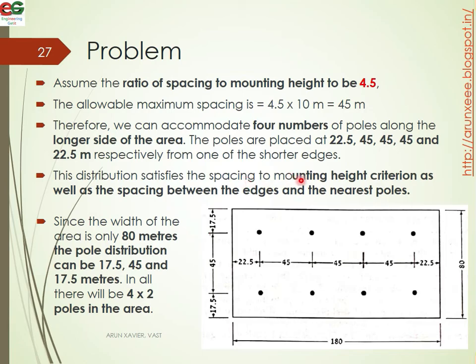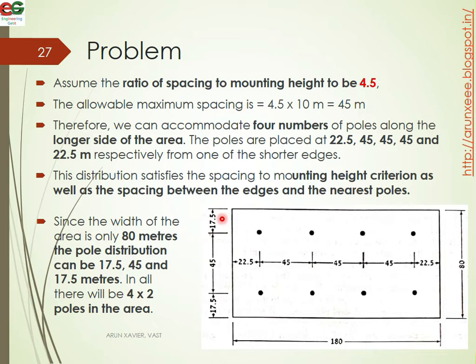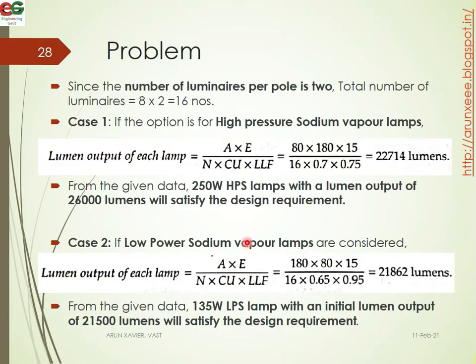This distribution will satisfy the spacing-to-mounting-height criteria as well as the spacing between the edges and the nearest pole. We split the width and length accordingly. The number of poles is equal to 8, and since we need 2 lamps per pole, the total number of luminaires is 8 times 2, which equals 16.